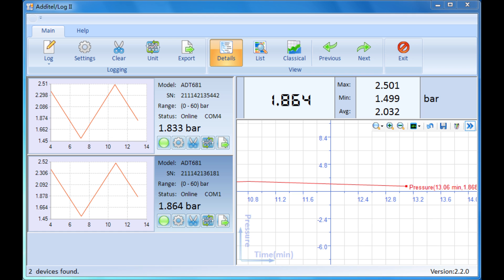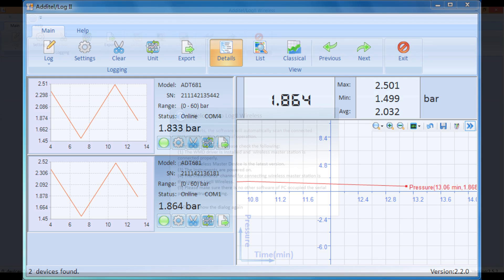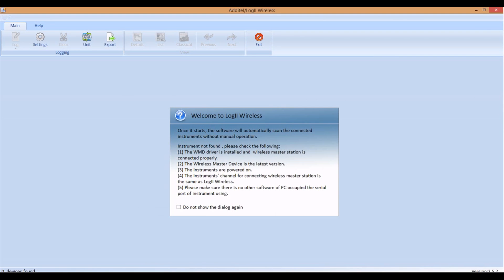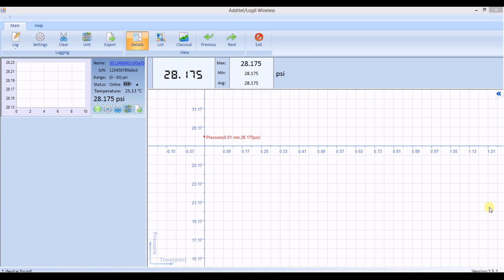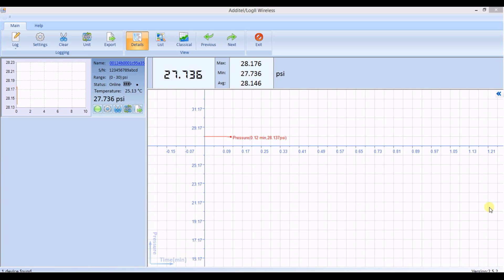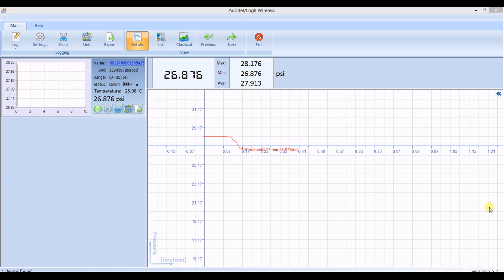Additel Log2 Wireless is an optional software package that gives you the capability to run a real-time log session with the ADT680W. Ensure the wireless function is activated on the ADT680W and the wireless master receiver is plugged into a USB port on the computer. Open the application and wait for the wireless connection to be established. You'll know the connection is established when the wireless icon in the gauge stops blinking and the logging graph appears.